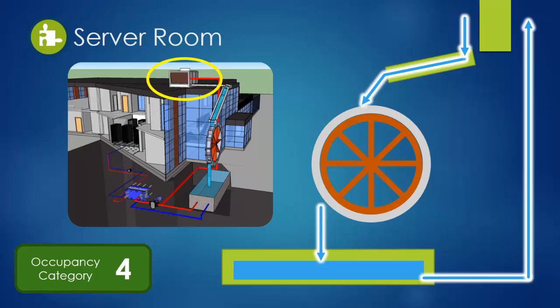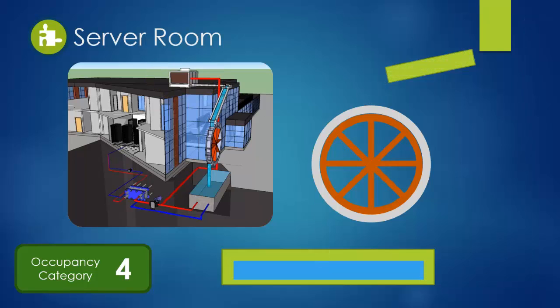If the water wheel is unable to cool the water to the correct temperature, the water-to-water heat pump will assist in the cooling process. If the water supply is depleted, the water-to-water heat pump will provide all necessary cooling. This unit will be placed underneath the raised floor in the server room and cannot be seen in the figure. The water basin will act as a waterside economizer when outside conditions are optimum. When the outside temperature drops below 40 degrees Fahrenheit, the water basin will be heated to prevent freezing.